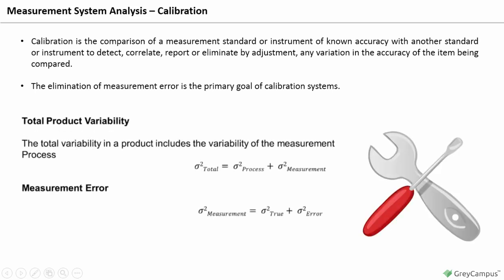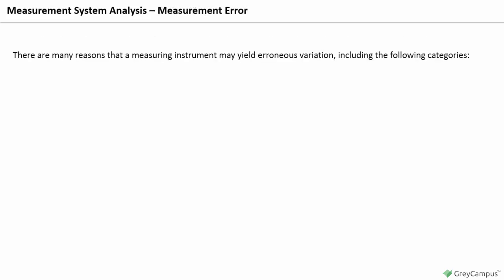Total product variability. The total variability in a product includes the variability of the measurement process. Variance, that is total, is equal to variance in the process plus variance due to measurement. Measurement error. Variance in measurement is equal to true variance plus variance due to error. There are many reasons that a measuring instrument may yield erroneous variation, including the following categories.